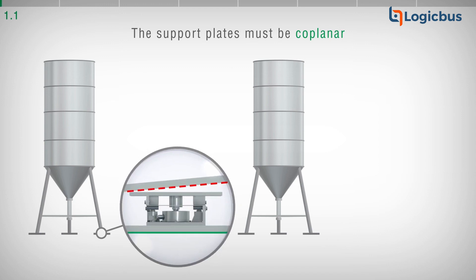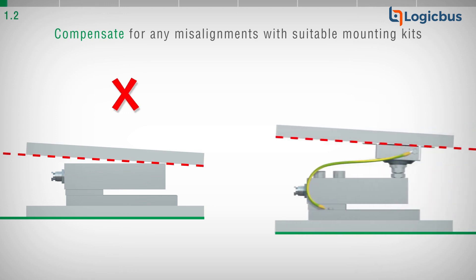Check that the load cells support plates are coplanar and, as a rule, planar. Use suitable mounting kits to compensate for any misalignment of the support plates.